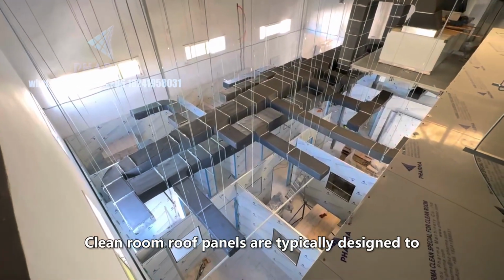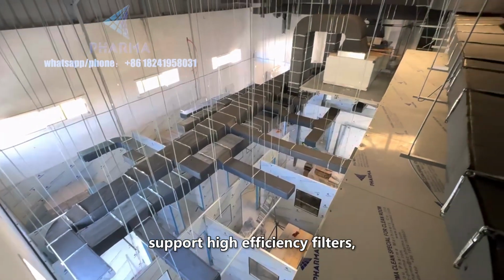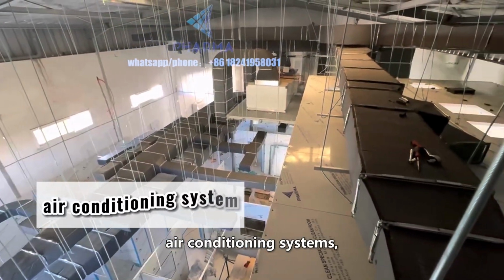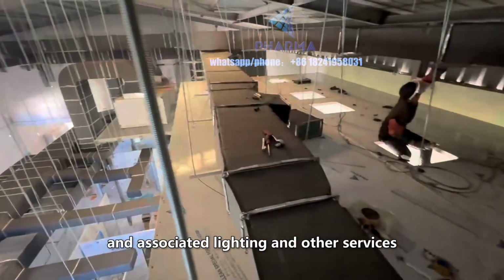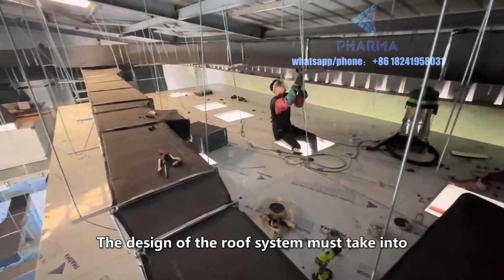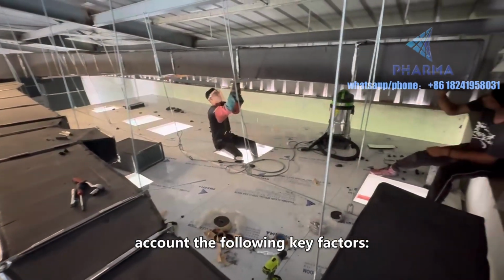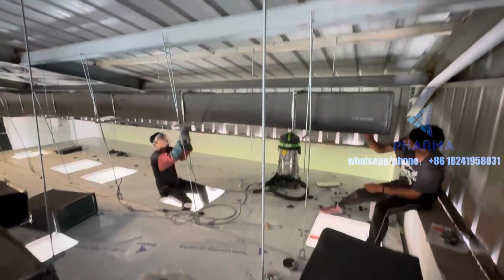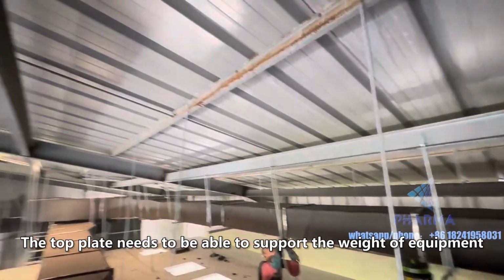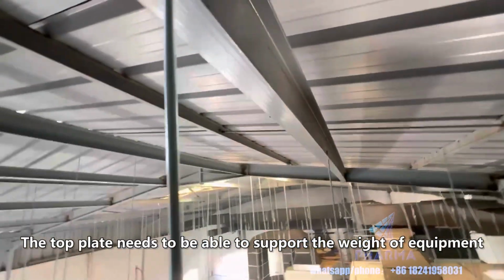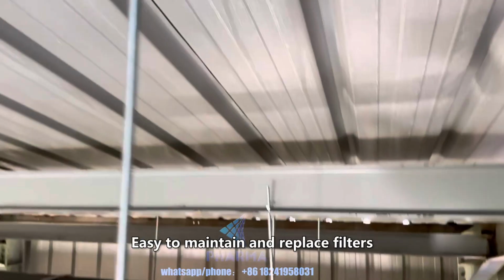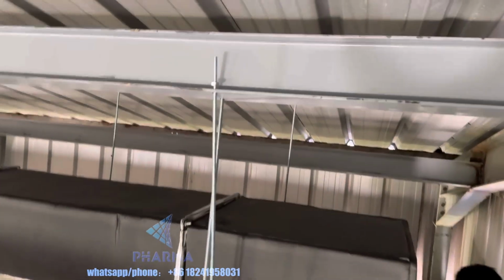Cleanroom roof panels are typically designed to support high-efficiency filters, air conditioning systems, and associated lighting and other services. The design of the roof system must take into account the following key factors. Support capacity: the top plate needs to be able to support the weight of equipment such as filters and lights. Modular design, easy to maintain and replace filters.